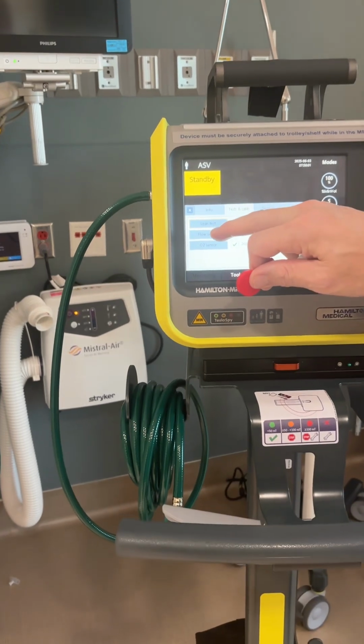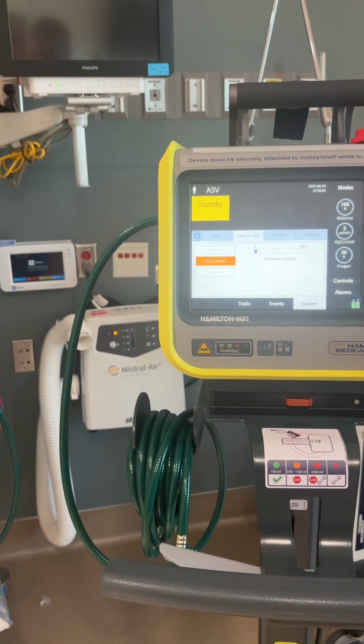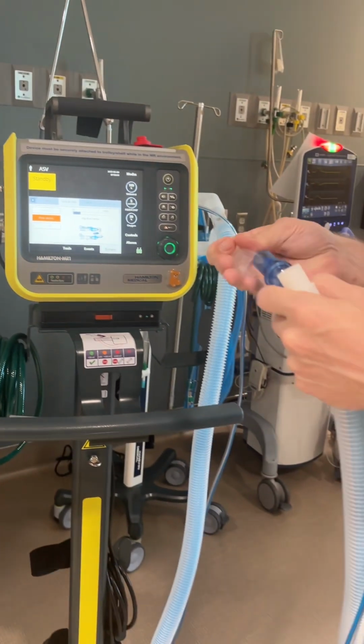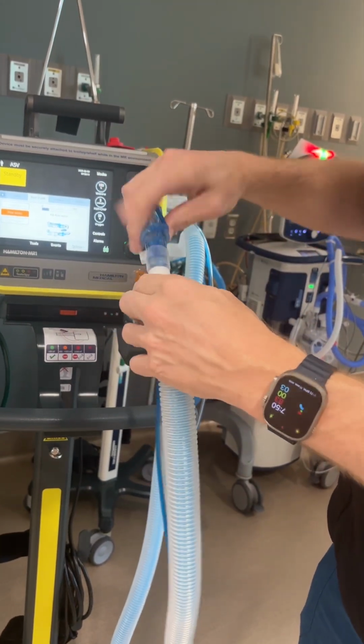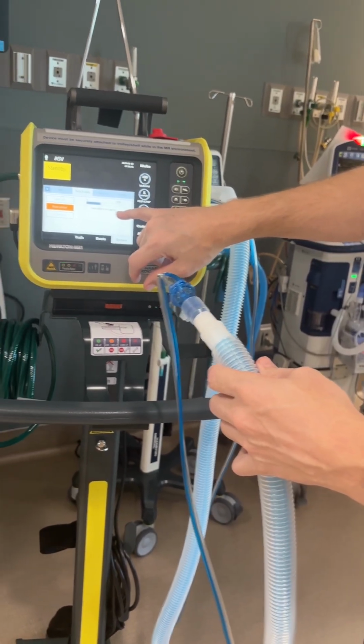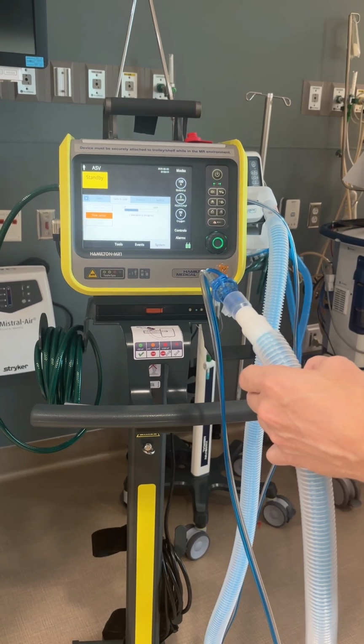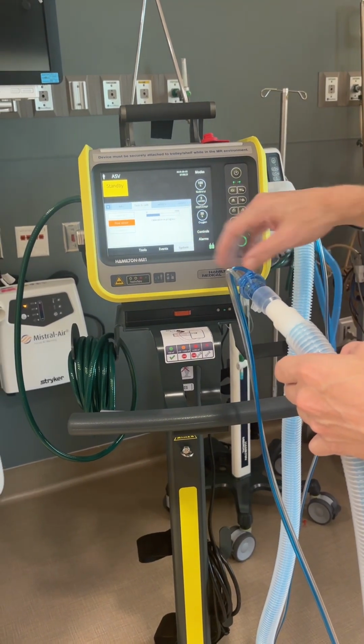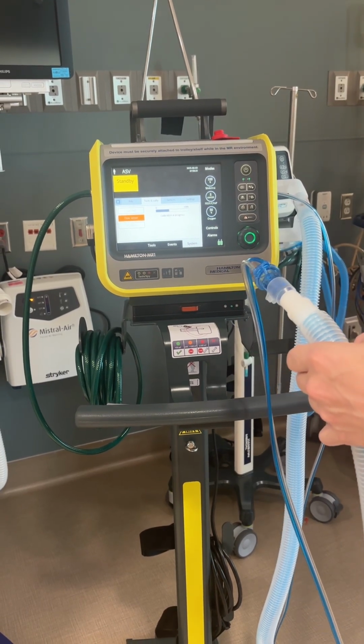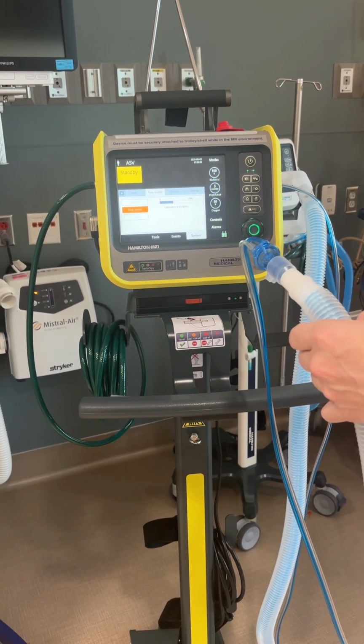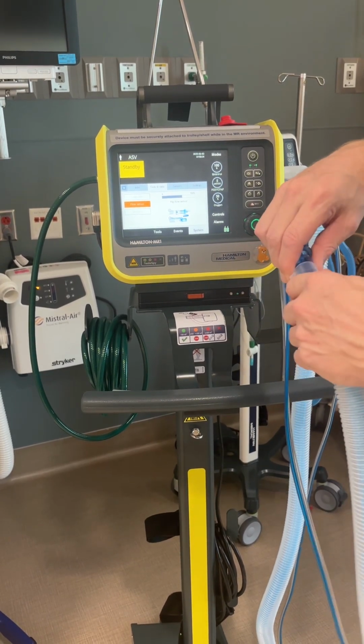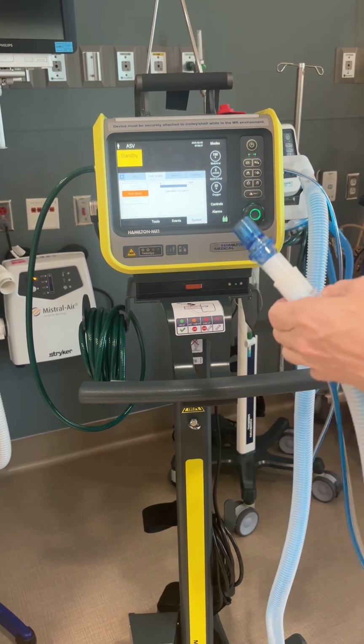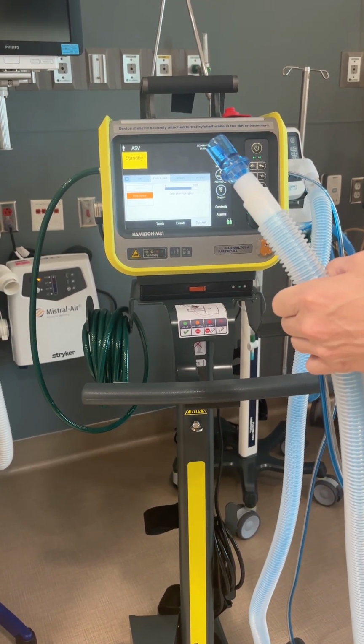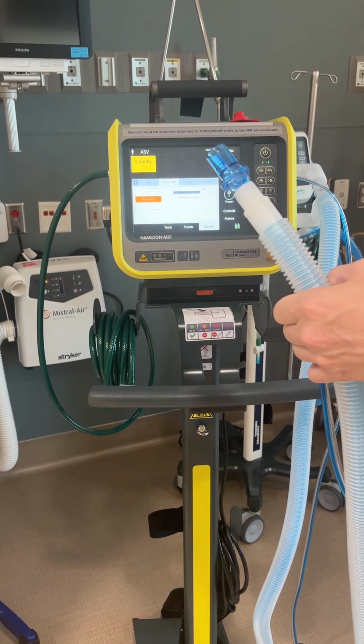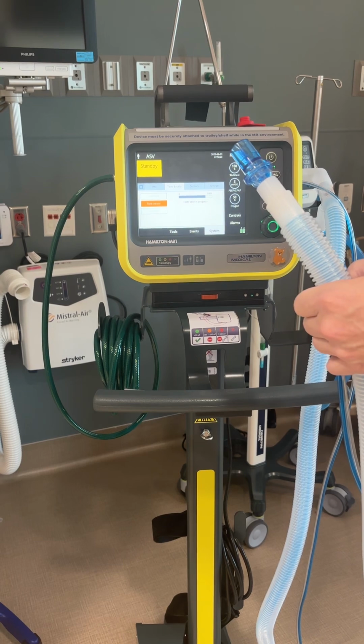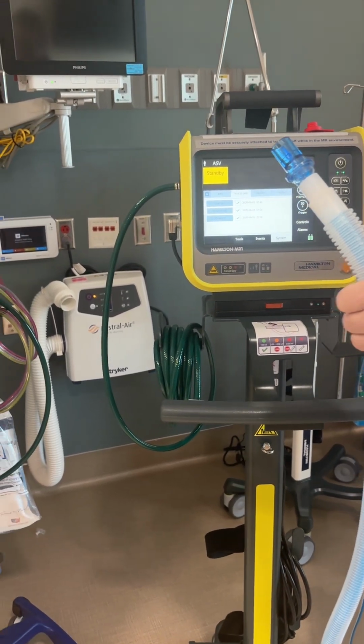Now the flow sensor. You're going to disconnect the patient, and it's going to ask you to flip the flow sensor. This is where you use your little thing right here, and you're going to flip it right here. And it'll automatically register that it's flipped. You have to be kind of fast with it, because it will fail if you don't do it in a certain amount of time. But you can always go back and redo it. And then you're going to flip the flow sensor back. You can take this one off, and it's going to finish calibrating. And then you can see how it's done.